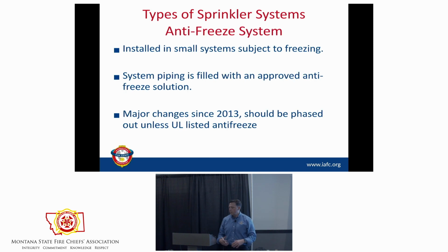We put these in like computer rooms, and we used to allow these things called antifreeze, and I'm sure in Montana you still have them. NFPA over the last 10 years has said stop using antifreeze. Why? Antifreeze is a combustible, flammable, or it's not any of those liquid. It is a combustible liquid, okay? So if you want to ignite a combustible liquid, do what to it?